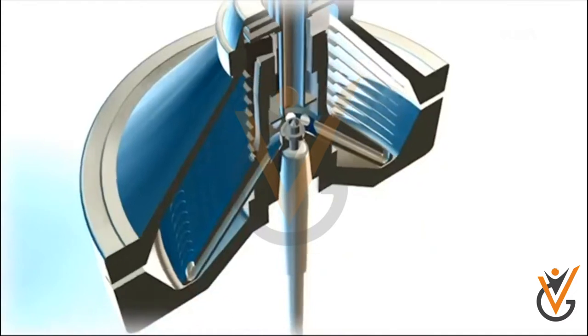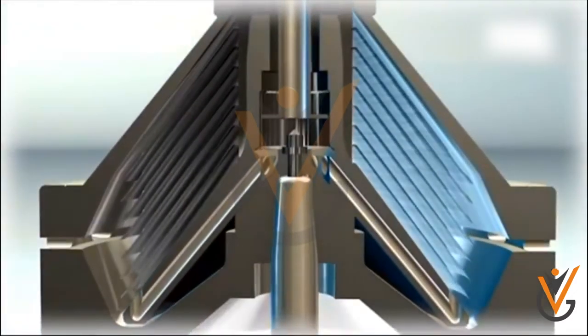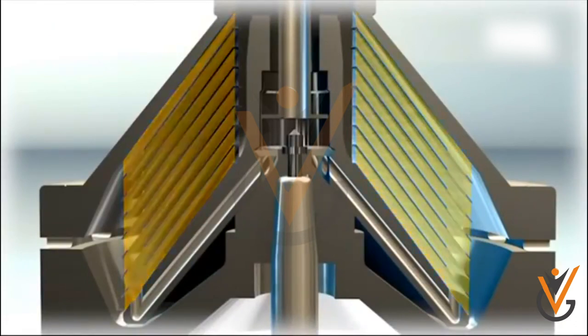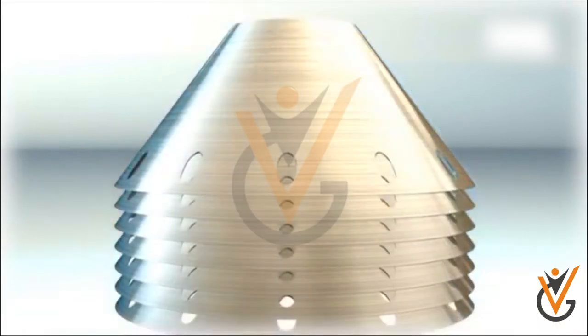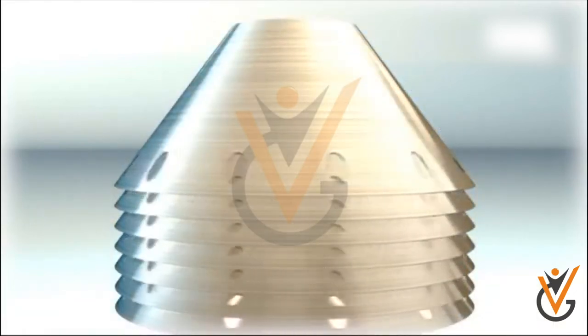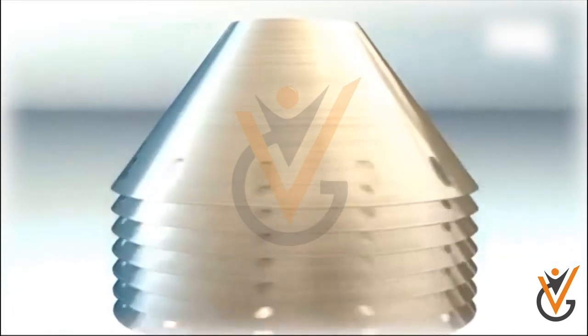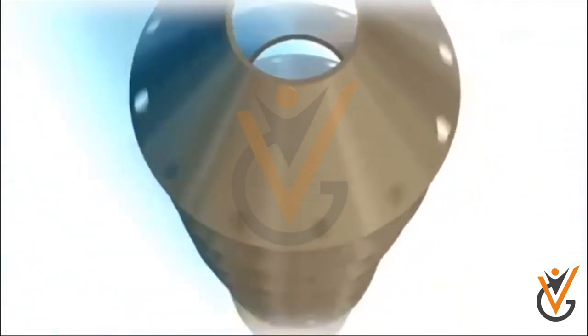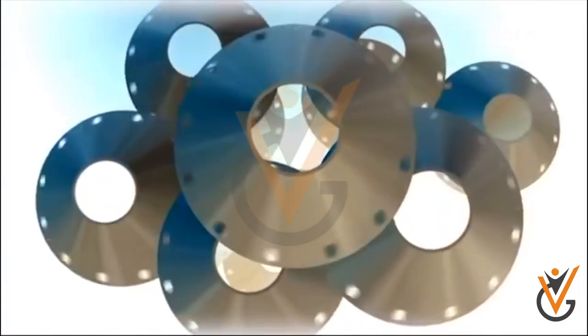Conical disc: Number of conical discs are fitted and covered by the conical hood. Distribution holes are also provided in those discs. The disc stack consists of a large number of vertically arranged, conical individual discs. Bars mounted on these conical discs keep them spaced apart to produce gaps between the discs. The disc stack is used to separate the product stream of oil into many partial streams.